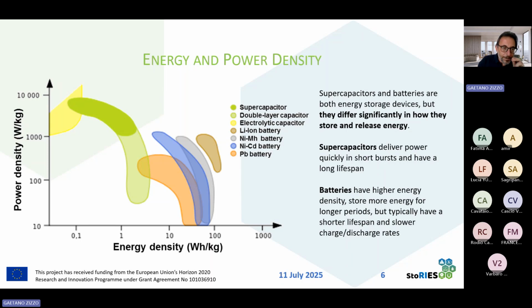As you can see in the figure, capacitors belong to the left part of the graph, so they have lower energy density. You see in this figure usually lower than 5-6 watt-hours per kilogram, but they have a very high power density that is usually between 50 and over 10,000 watts per kilogram. So they are perfect for delivering services, for example, related to frequency regulation, or better, to virtual inertia, a service that I will show you later.